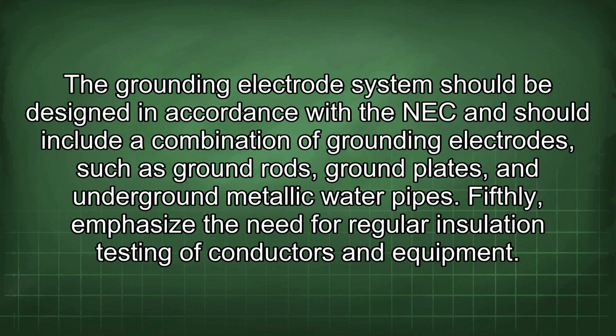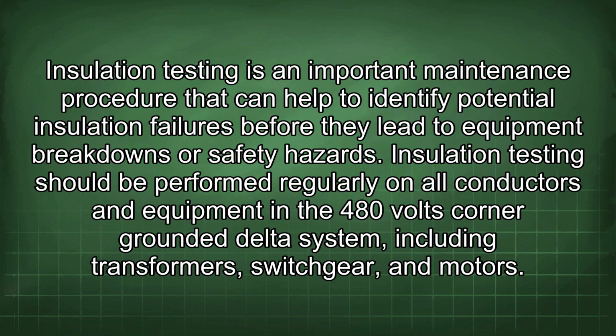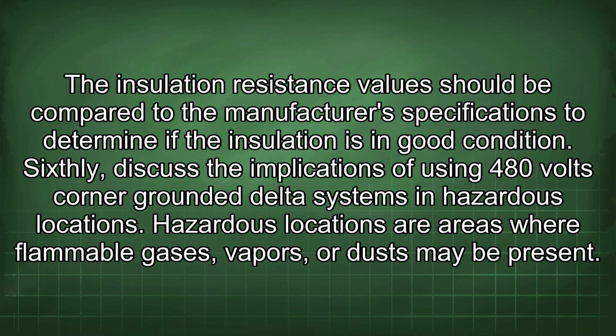Fifthly, emphasize the need for regular insulation testing of conductors and equipment. Insulation testing is an important maintenance procedure that can help to identify potential insulation failures before they lead to equipment breakdowns or safety hazards. Insulation testing should be performed regularly on all conductors and equipment in the 480 volts corner-grounded delta system, including transformers, switchgear, and motors. The insulation resistance values should be compared to the manufacturer's specifications to determine if the insulation is in good condition.